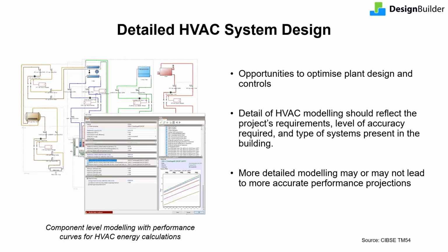In the earliest stages of design, it is generally okay to use simple HVAC, as the additional time involved in detailing out the HVAC system may not be justified. However, if the modeling is being done at advanced stages of building procurement, when the system details are available and are finalized, then detailed system modeling would typically be helpful.